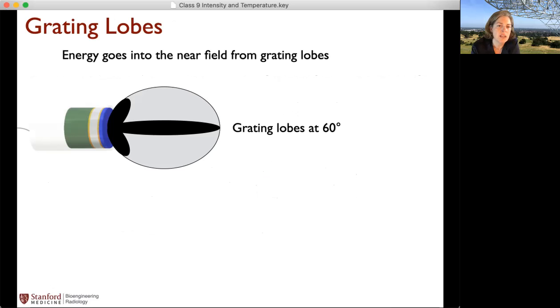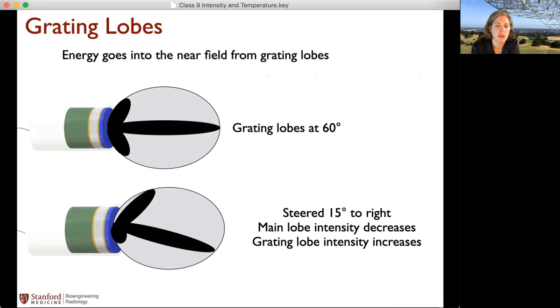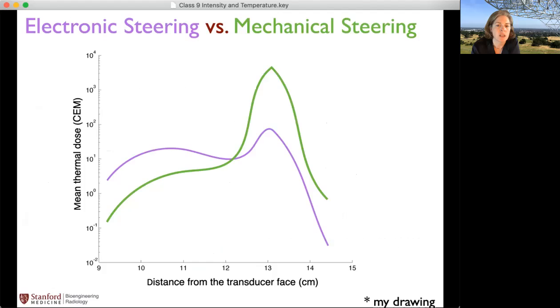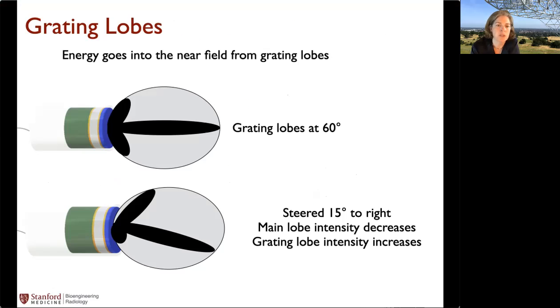The other reason has to do with those grating lobes. So remember we talked about the presence of the grating lobes and how, as you steer the beam to the side, both the main lobe and the grating lobes are kind of going around this oval as you see here. So you steer to the side. And so what's happening here is that as we steer to the side, that grating lobe is increasing and it's putting more energy into the near field. Right, so that's exactly falling out from this picture: we steer to the side in order to get to the target. That near field adjacent to it is getting heating just from that grating lobe as it's increasing.